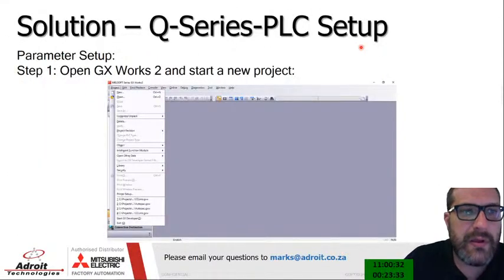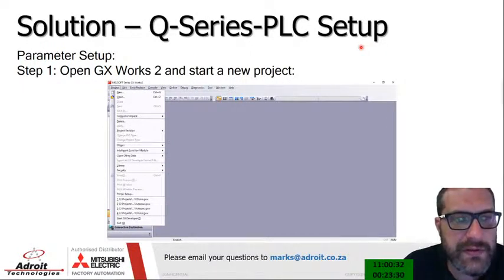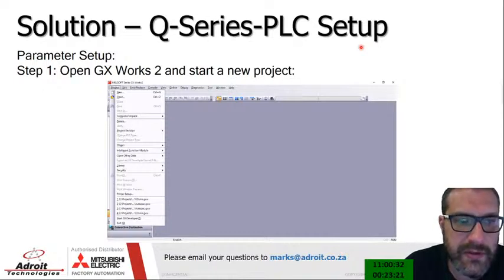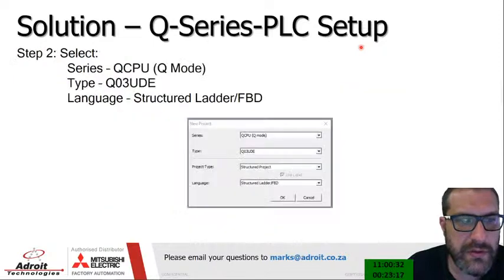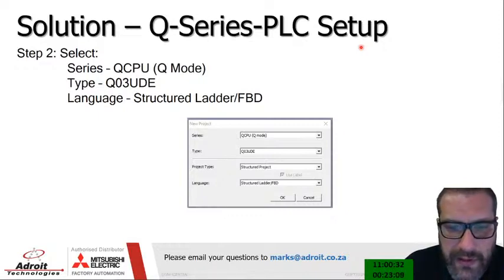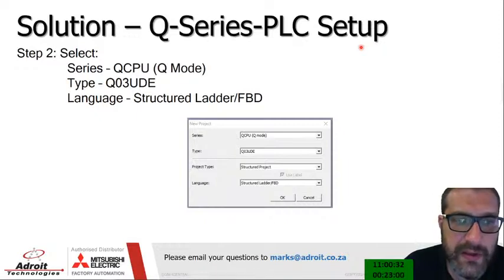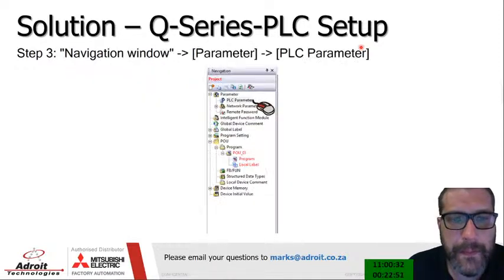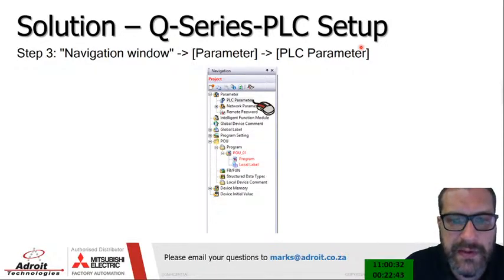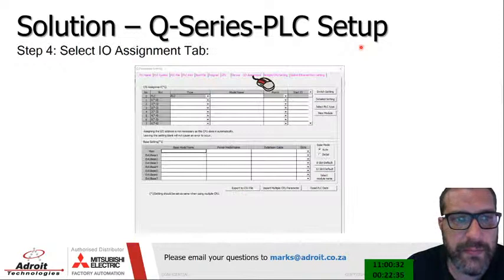To set up the Q series PLC in GX Works 2, step one is to open a new project — go to Project > New, then select your actual PLC type. In this example I used a Q03UDE, but you can use a Q02, Q05, Q18, or others. I use structured ladder/FBD as my language. Before doing anything else on a PLC, always set up the parameters first — go to the navigation window, then Parameter > PLC Parameter.